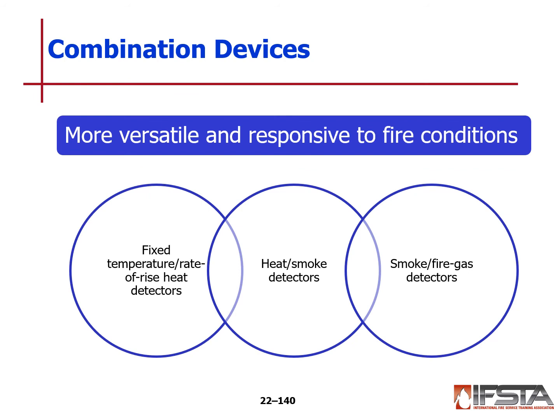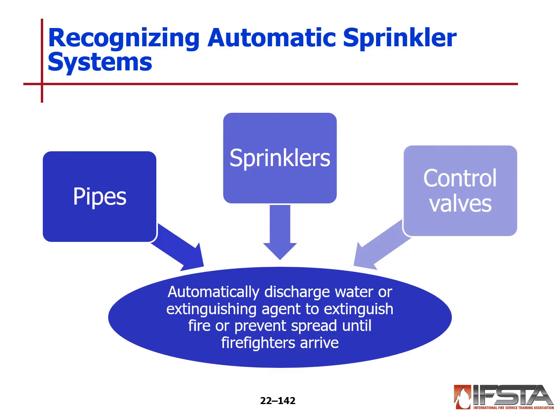Combination devices are more versatile and responsive to fire conditions. Your fixed temperature and rate of rise heat detectors can be combined with smoke and heat detectors, as well as fire gas detectors. Automatic sprinkler systems. Recognizing this, we have pipe, sprinklers, and control valves. The combination of these automatically discharge water or extinguishing agent to extinguish a fire or to help prevent the spread until firefighters arrive.